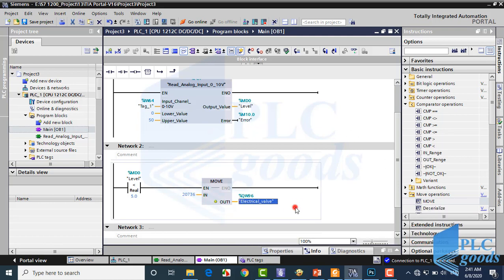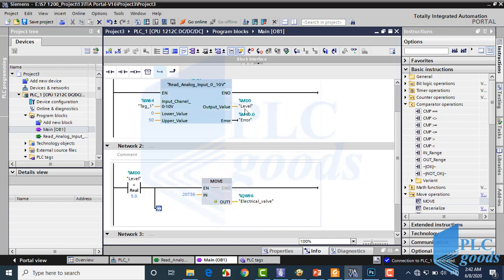At the second network, if the level is less than 5, then the MOVE instruction sends the number 27648 to the analog output. Otherwise it will be 0 to have 4 mA at the output.